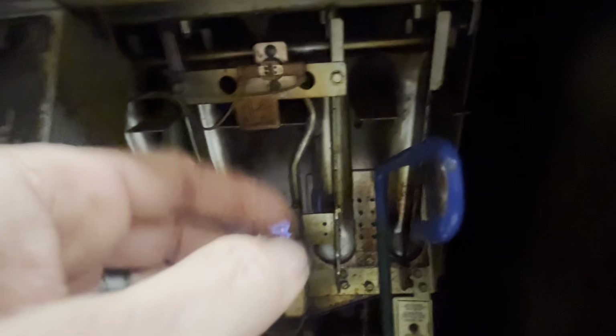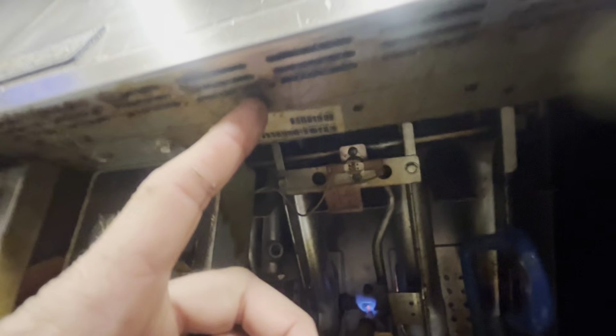We could actually have self-burning. With these units, there's a self-cleaning tube that comes on, and then it runs across the top and it burns the orifices, and it's allegedly to keep those orifices clear of debris. So either our orifices are clogged up, or our burner covers are clogged up, or we just have crap gas pressure. But this unit can't recover.